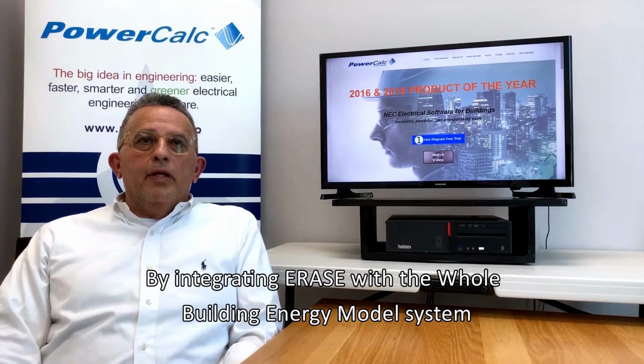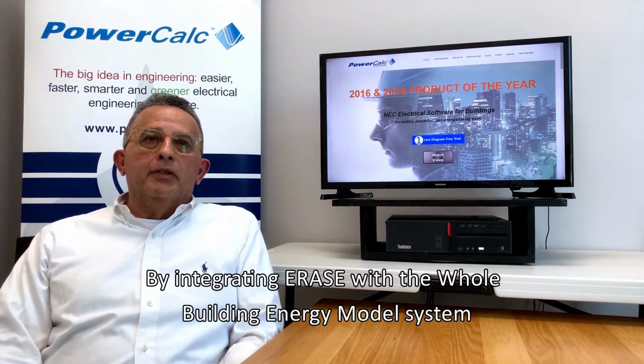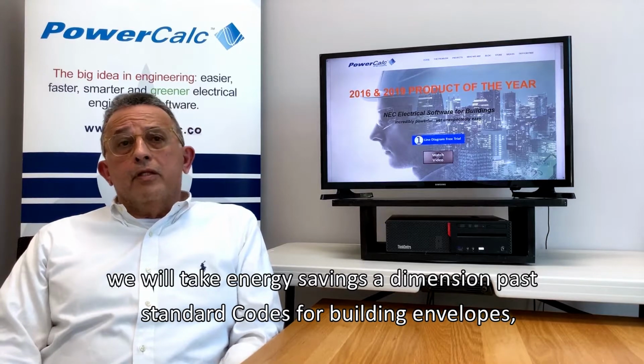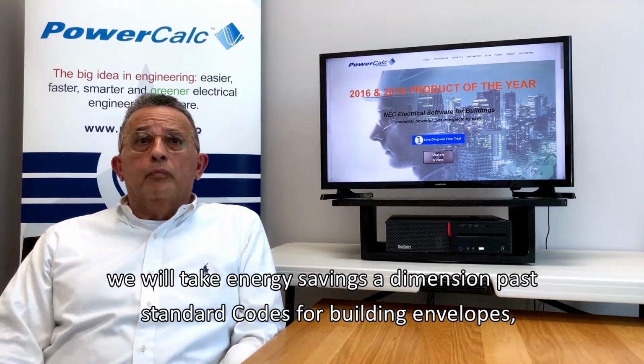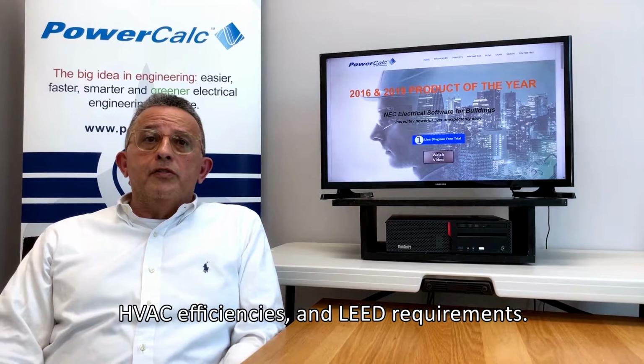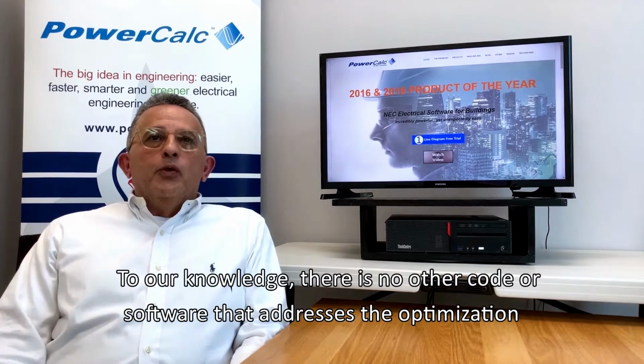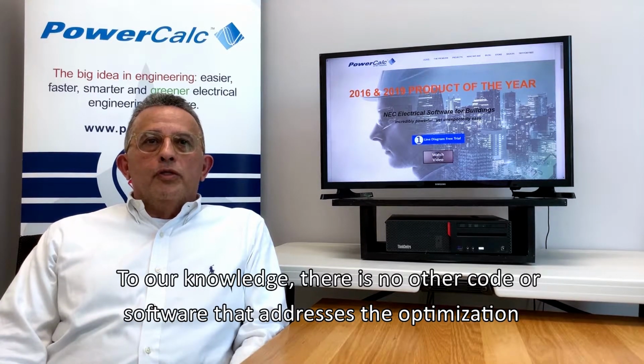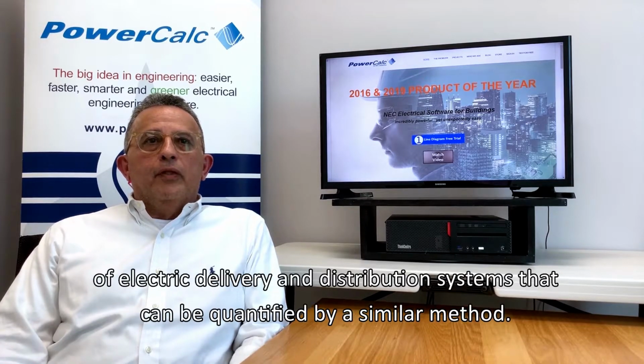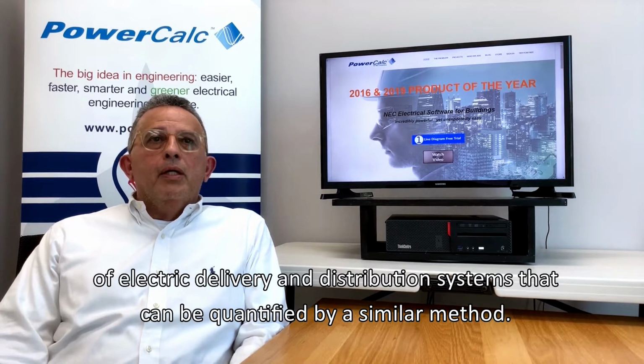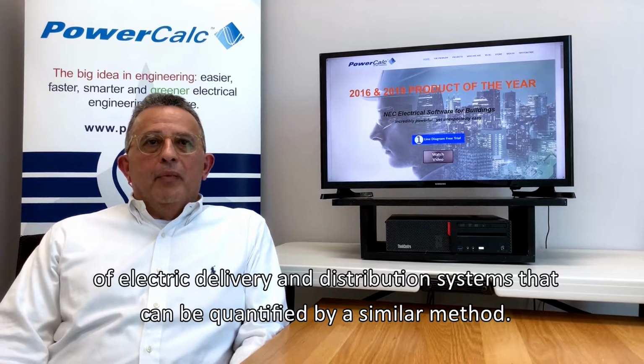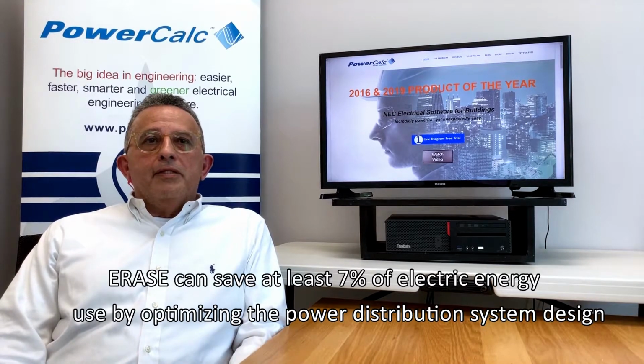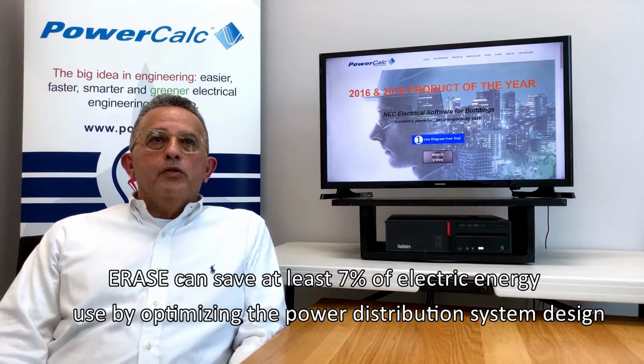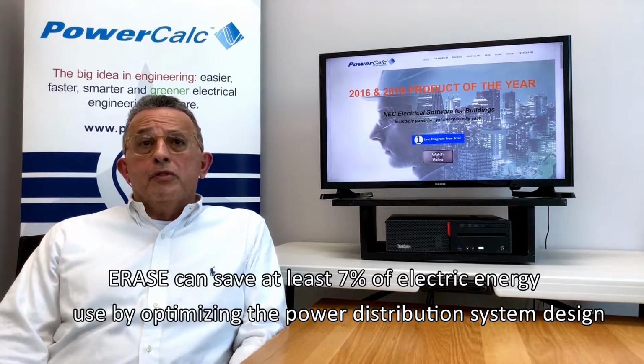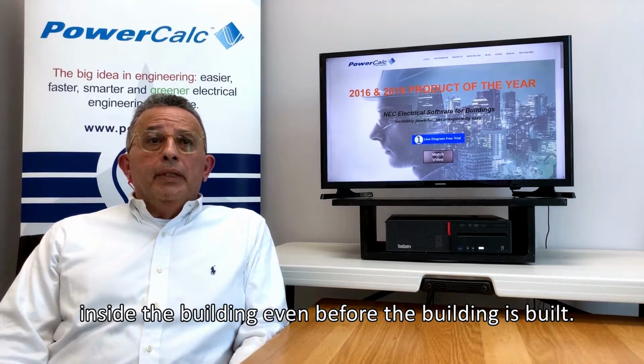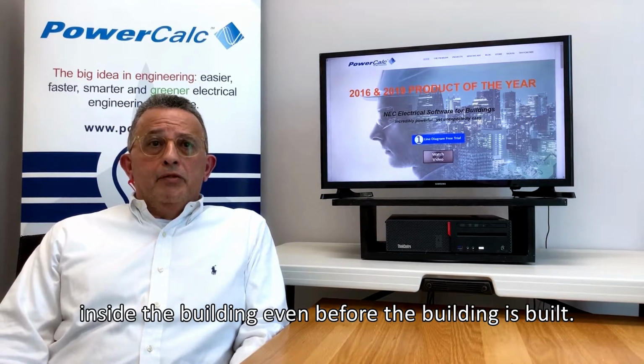By integrating ERASE with the whole building energy model system, we will take energy savings a dimension past standard codes for building envelopes, HVAC efficiencies, and LEED requirements. To our knowledge, there is no other code or software that addresses the optimization of electric delivery and distribution systems that can be quantified by a similar method. ERASE can save at least 7% of electric energy use by optimizing the power distribution system design inside the building, even before the building is built.